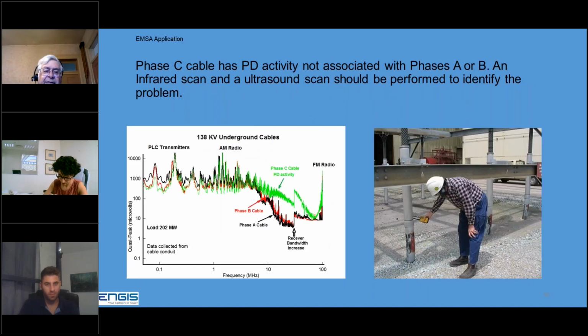Here's a 138 kV cable where they tie from the power plant into the grid. So this is quite some distance from the plant. And again, the transmission lines make excellent antennas. Power line carriers from the grid, AM radio stations, FM radio stations. Unlike partial discharge analysis, EMSA identifies all of these signals. And like I mentioned several times, they make good benchmarks.